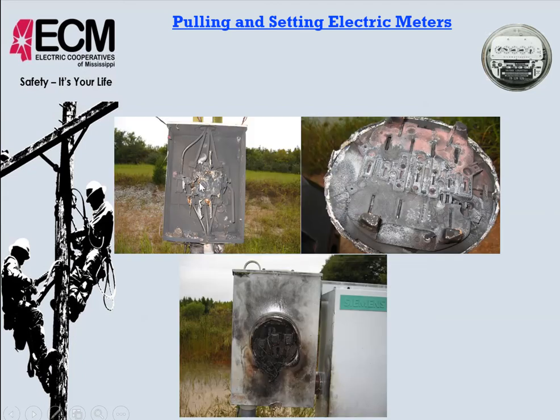This is where they set the 120/240 meter on a 480 service. And you see how devastating it was, burnt the meter up, burnt the lugs slam off of it, completely off of it. They're not even there anymore. Okay? And just burned up everything. Guy was injured, recovered. But definitely want to avoid that.